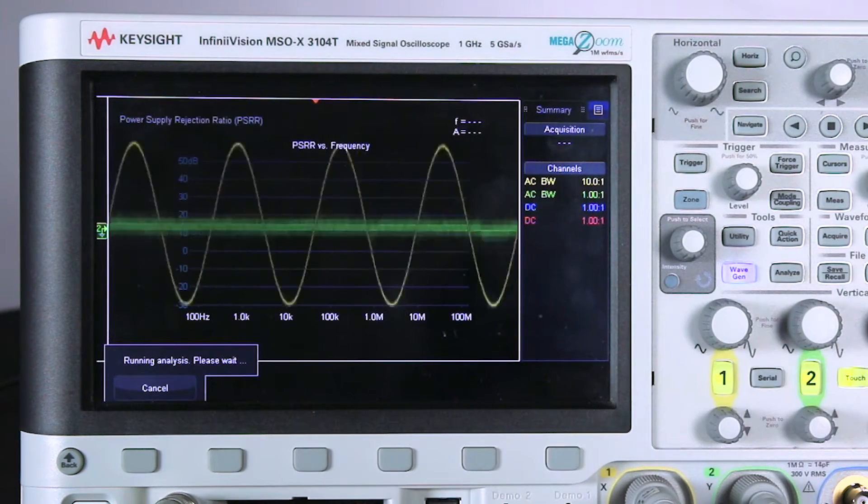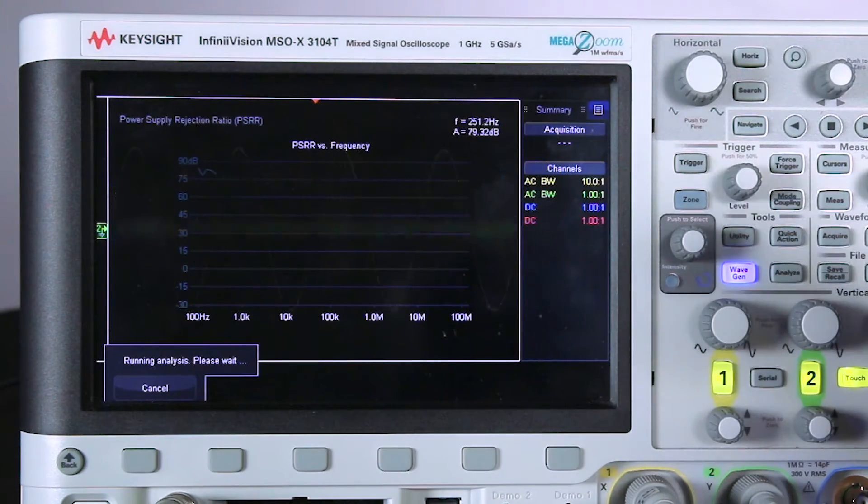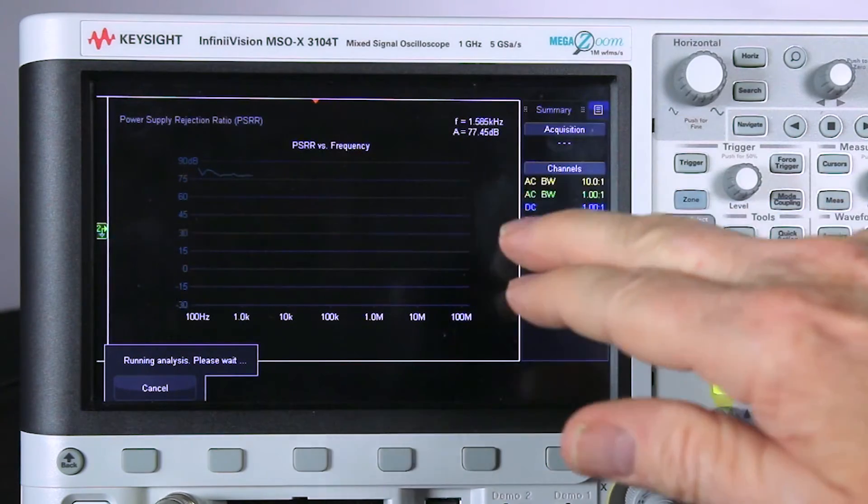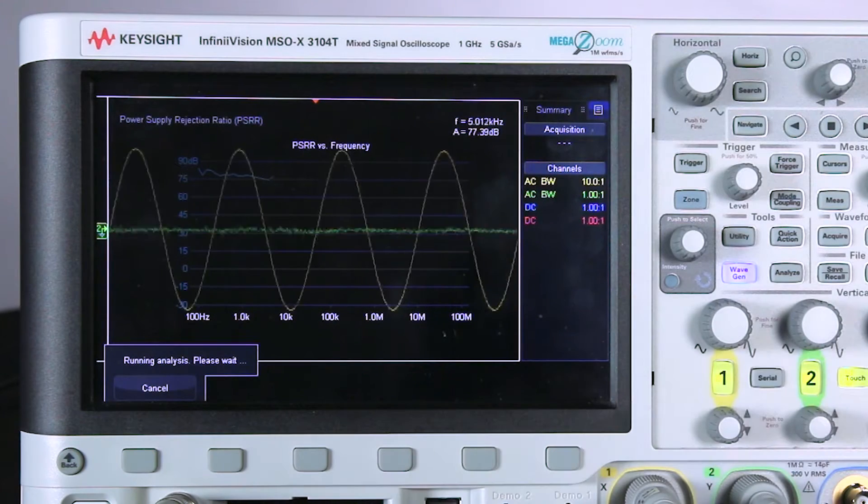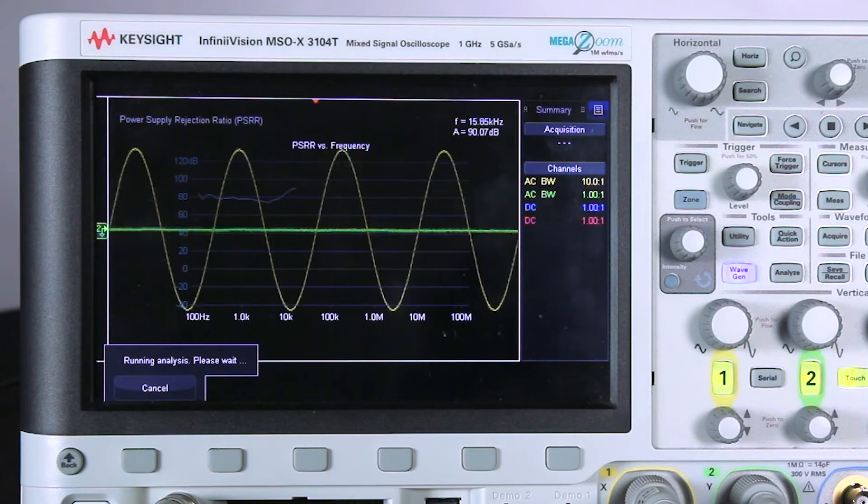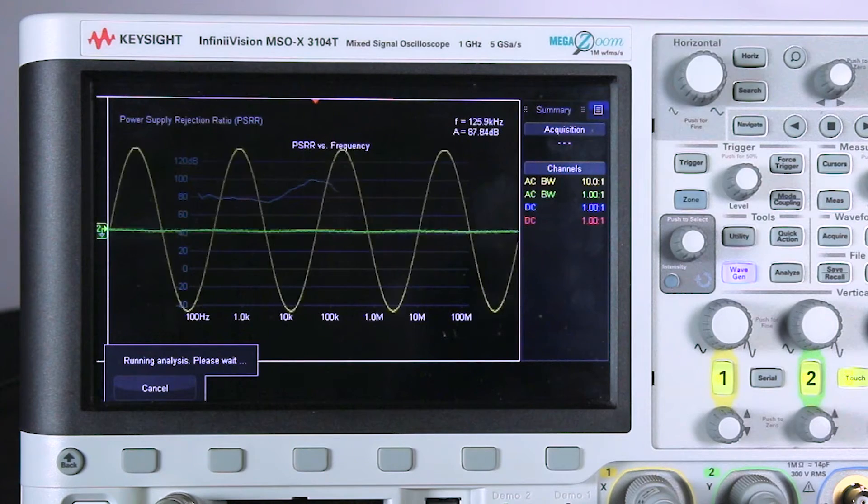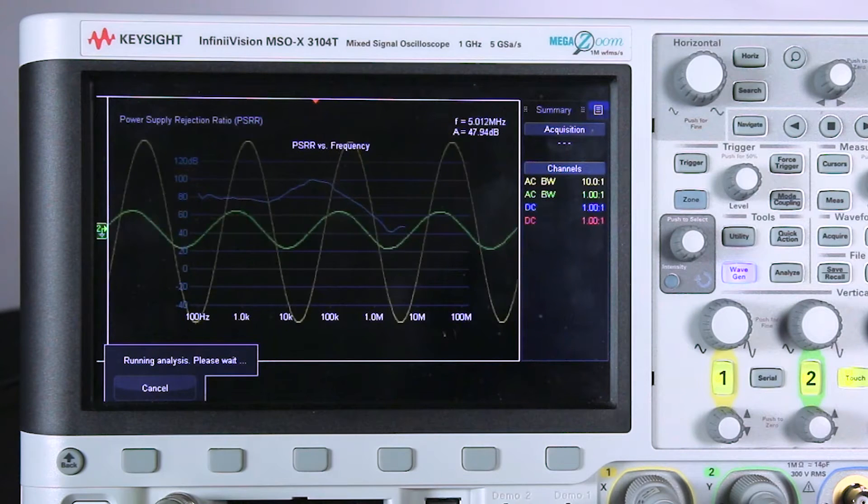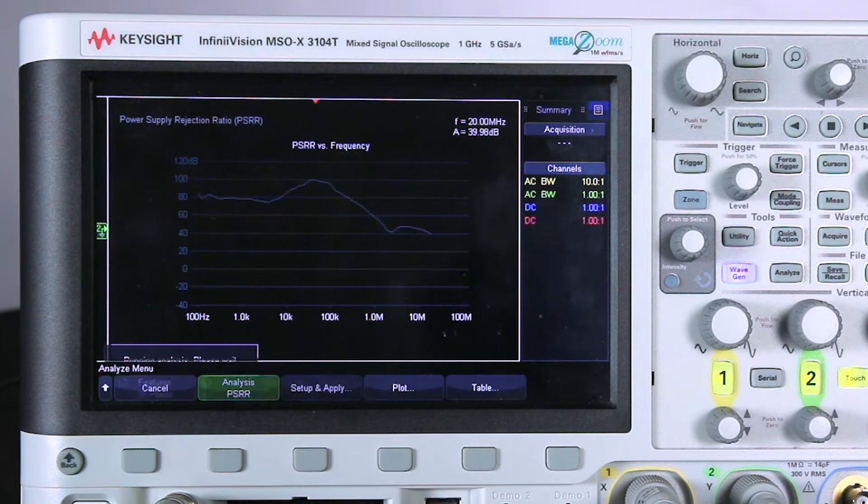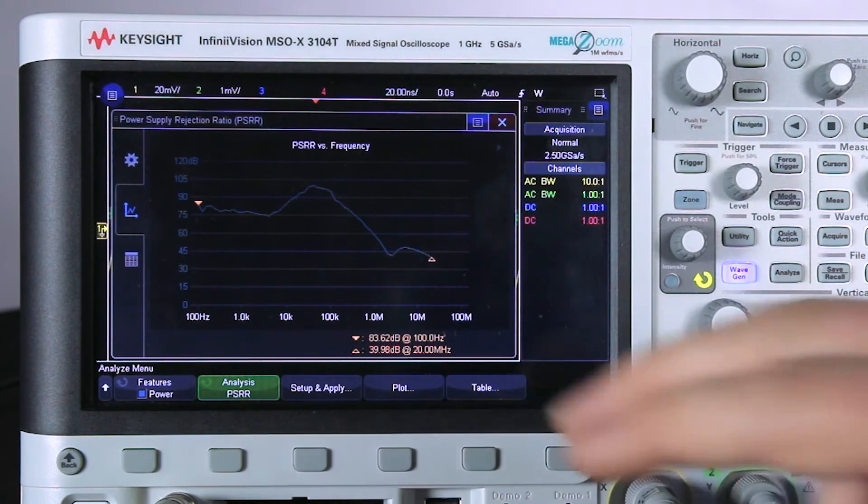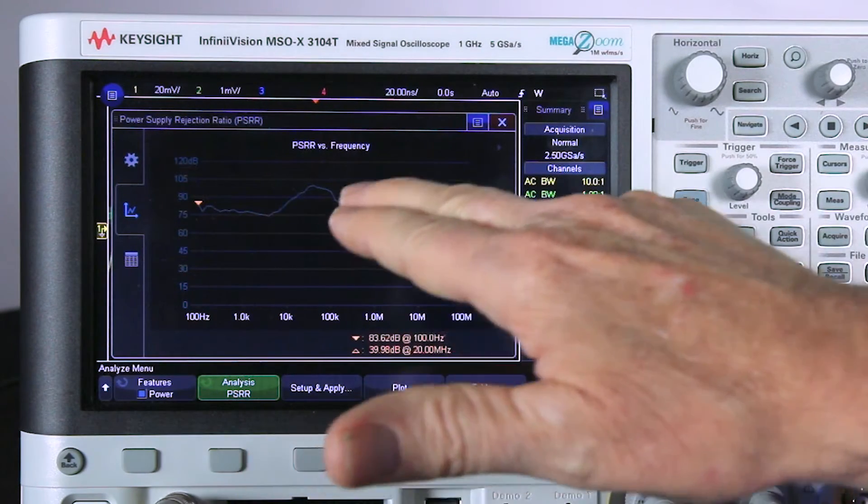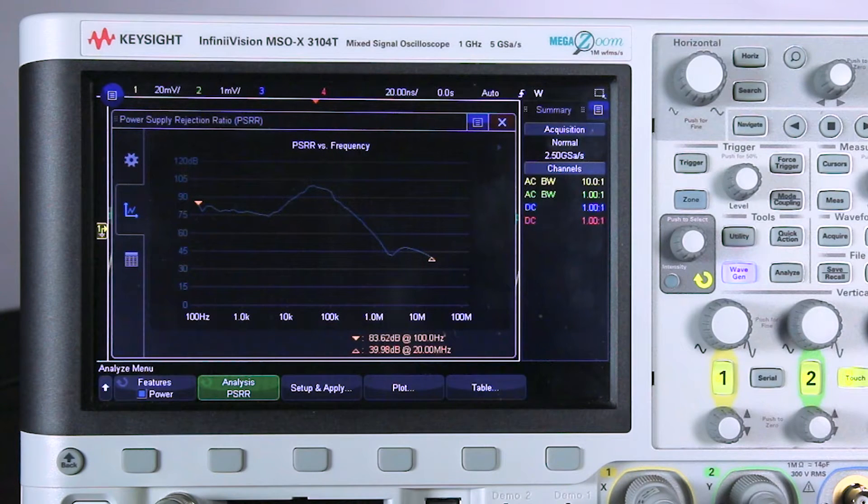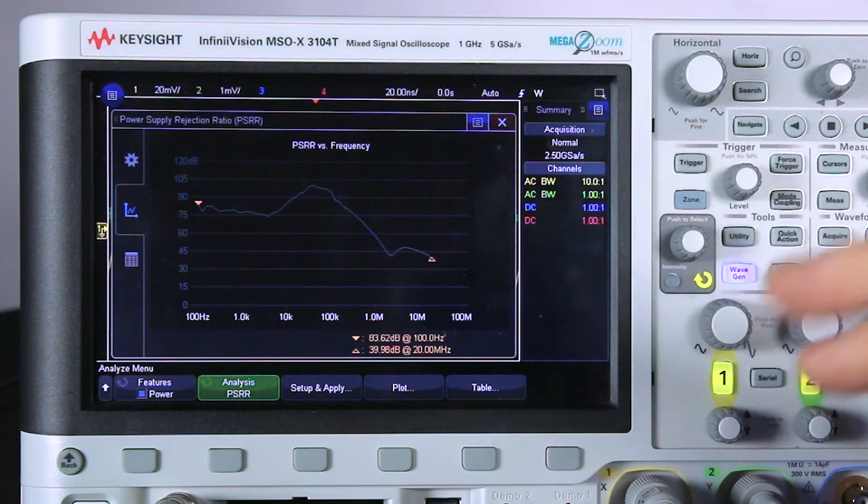One advantage of the scope-based solution is you can see the waveforms during the test. The reason that's important is you can monitor for any distortion that may be occurring. Now it looks like we're getting a pretty good measurement simply at the 200 millivolt peak to peak input. You notice it is a little wiggly in different areas. That is a signal to noise ratio problem.